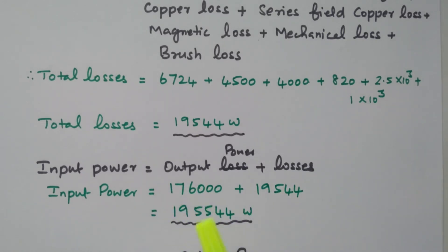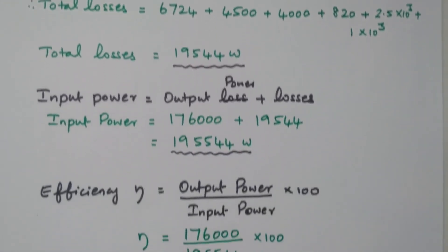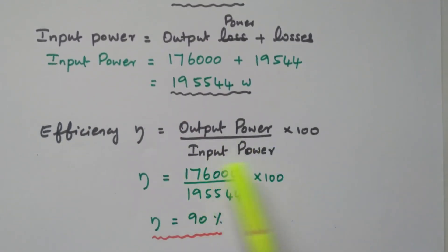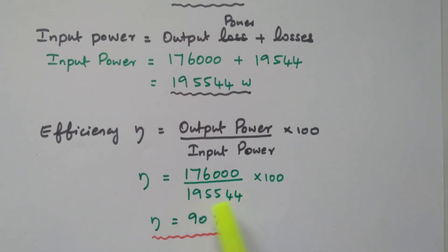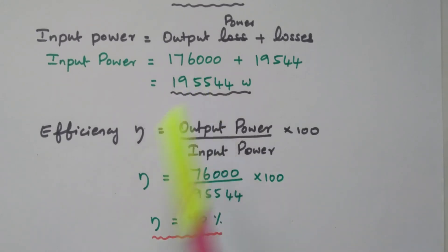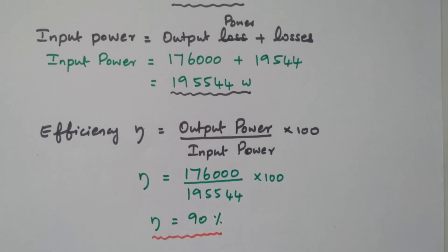Now we have output power and input power, so we can calculate the efficiency. Efficiency equals output power divided by input power, multiplied by 100. Output power is 176,000 divided by input power 195,544, into 100. By simplifying this, we get 90 percent.